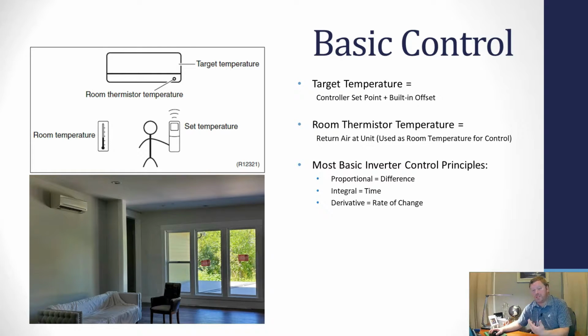What the system will do is calculate the difference between that target temperature and the return air temperature. So if the return air temperature is 65 because it's cold in the house, and you turned it on and cranked the set point up to 70, it's going to look at that 65-degree return air temperature and try to achieve a target temperature of 73.5. So that difference of 8.5 degrees is what's called the proportional part of the PID logic.